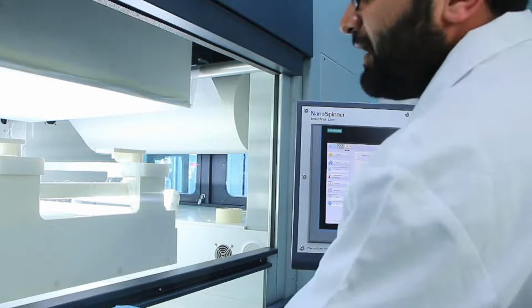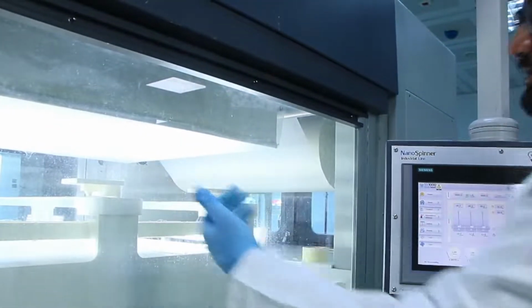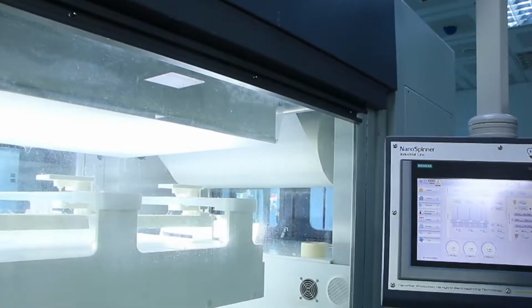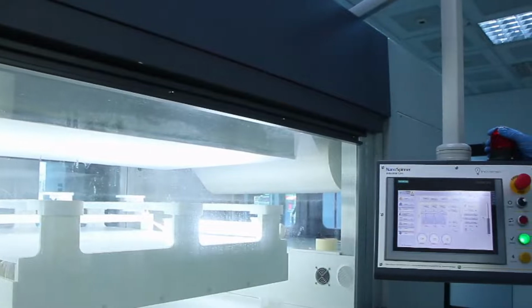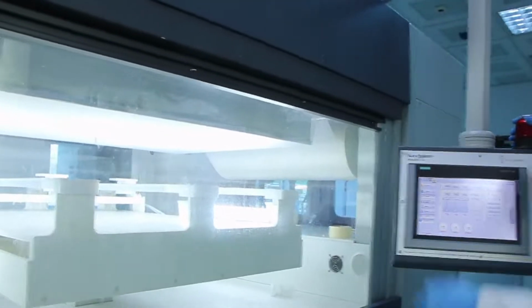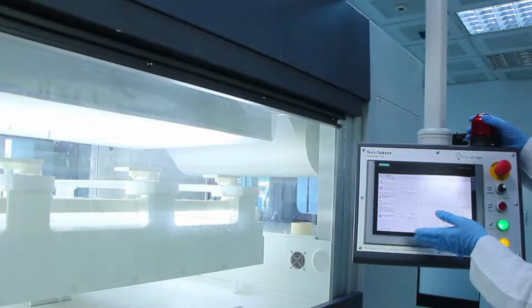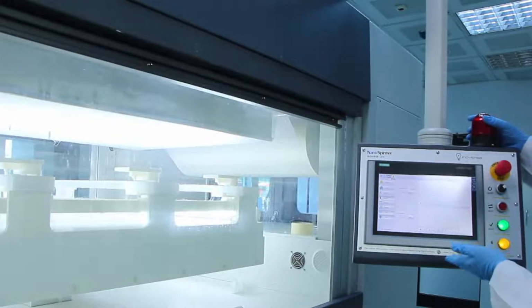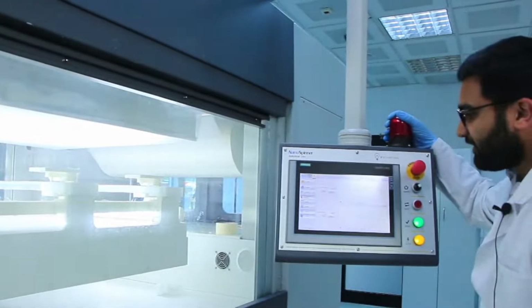In some cases, you might have to control the inside chamber. In which case, we have installed some heating units implemented here, and also dehumidifiers that you'll be able to see inside the machine. You can control from here. Basically, it's very similar to the graph that we mentioned. Right now, it's consistently stable because we haven't activated the heating unit or the dehumidifier yet.